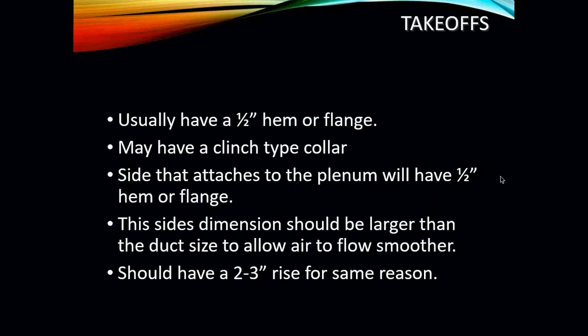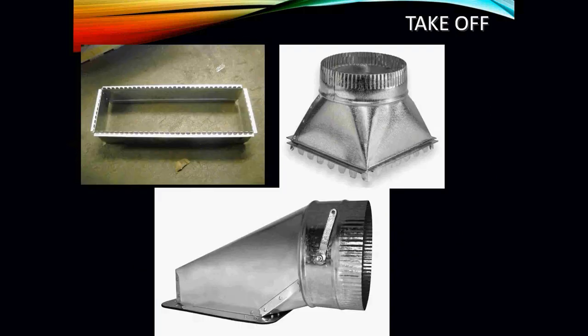Okay, your takeoffs, these guys are going to usually have a 1/2-inch hem or flange on them. Okay, they may be attached by a clinch type collar. Your sides that attach to the plenum will also have a 1/2-inch hem or flange on them. And the side dimensions should be larger than the duct size to allow air to flow much more smoothly. Okay, they should have a 2 to 3 inch rise for that very same reason.